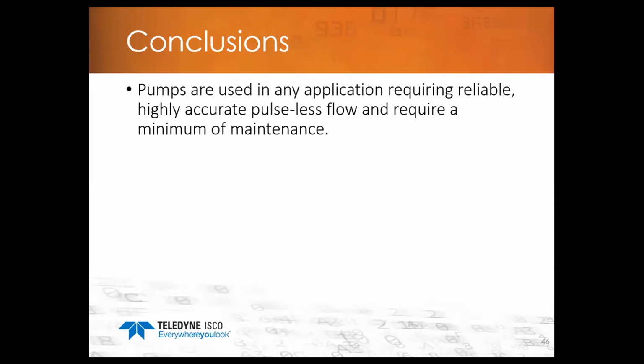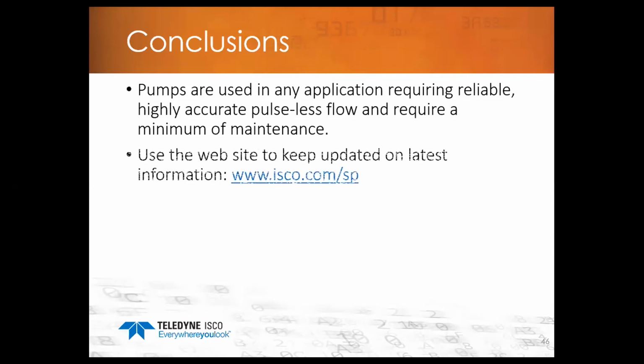But if you want to get into a once-a-year type maintenance thing, an annual PM type of maintenance, that would be fine. But I really don't have a figure for how long the seal should last, because that's going to vary with the application that you're running and the materials that you're running, as far as seal life is concerned. You can go to our website, www.teledyneisco.com, and on our syringe pumps, we have technical bulletins on field verification, pump maintenance, and a lot of information.